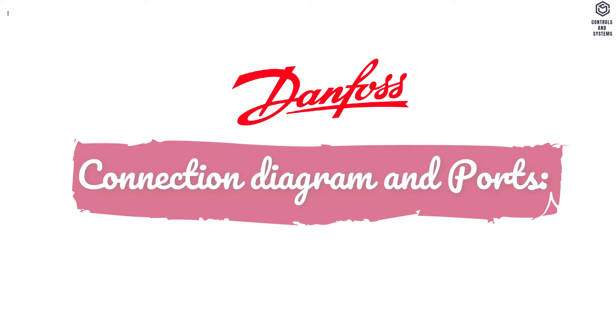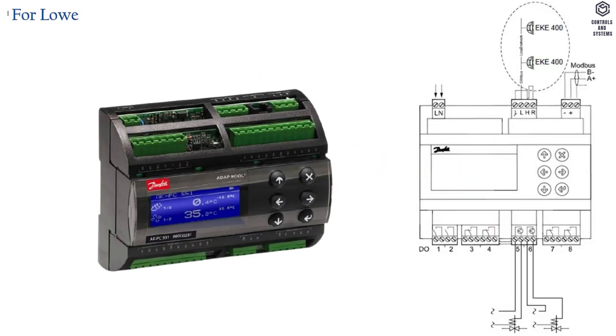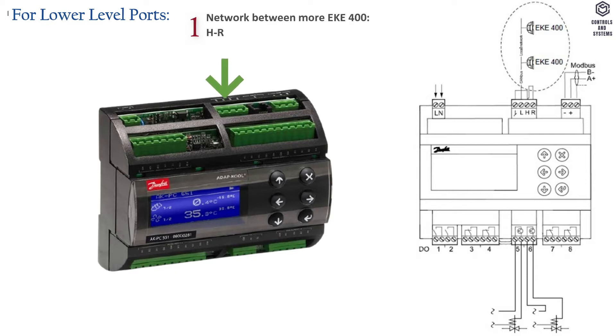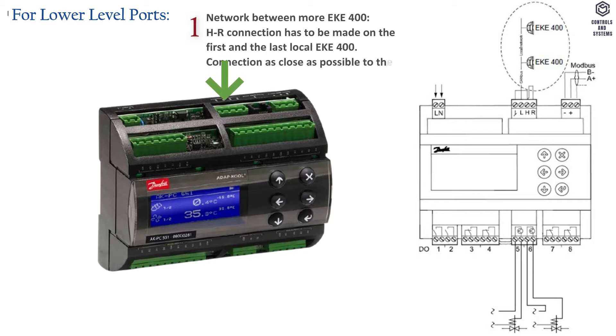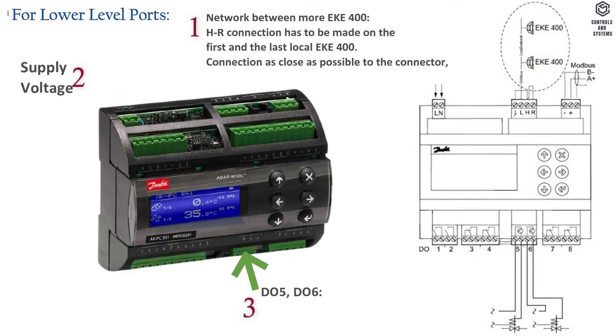Connection diagram and ports. For lower level ports: port 1 is the network between multiple EKE400 units — an HR termination resistor connection has to be made on the first and the last local EKE400, as close as possible to the connector. Port 2 is the supply voltage. Ports DO5 and DO6 are dedicated for PWM valves.